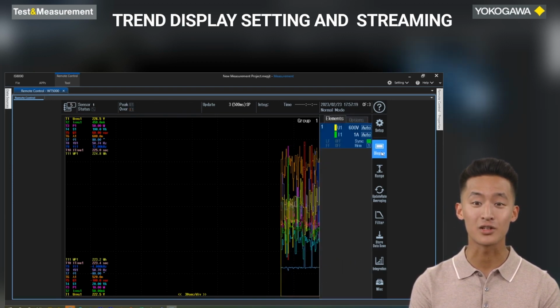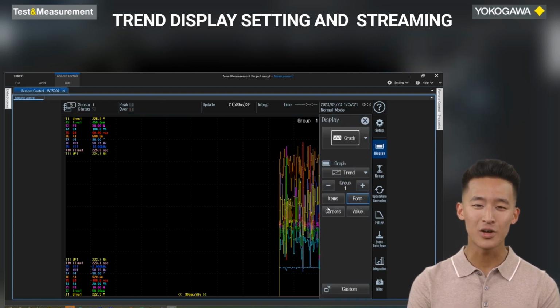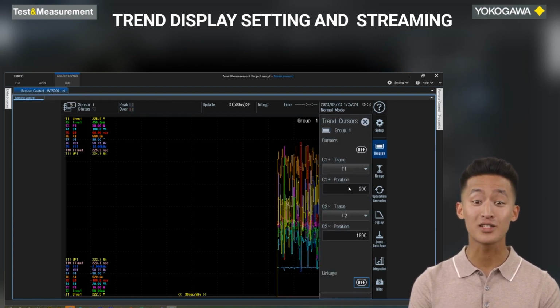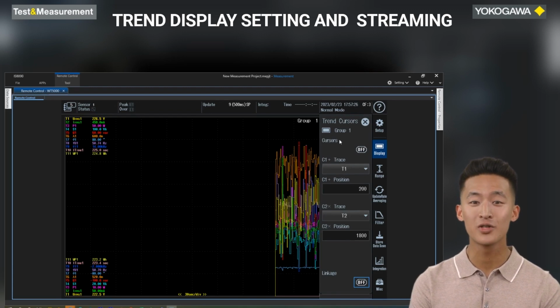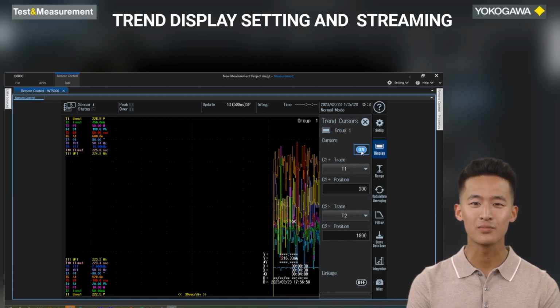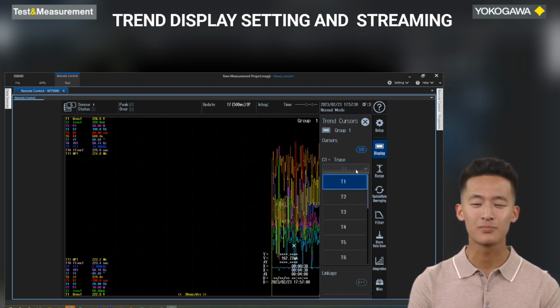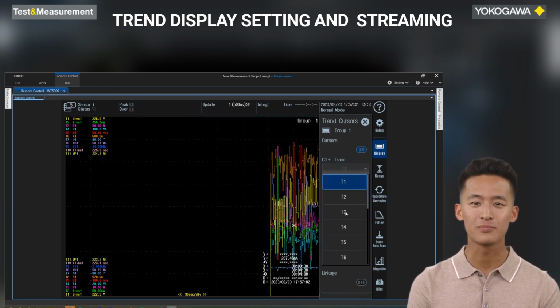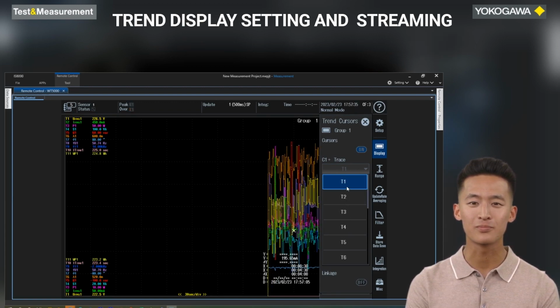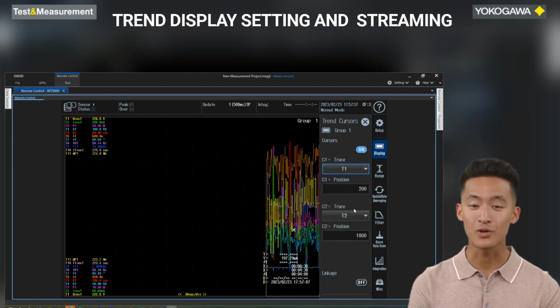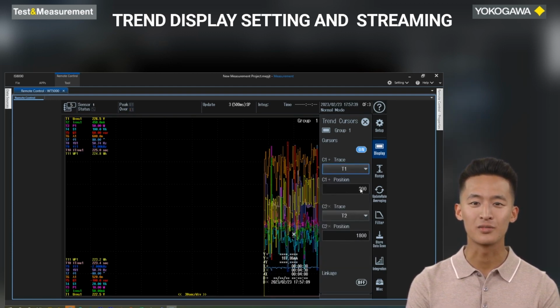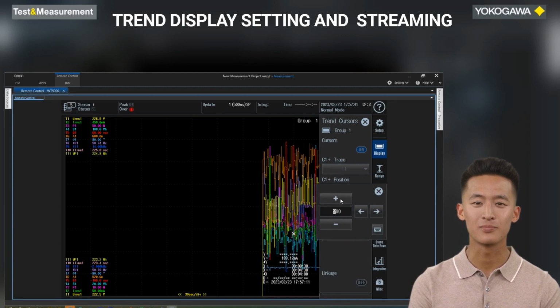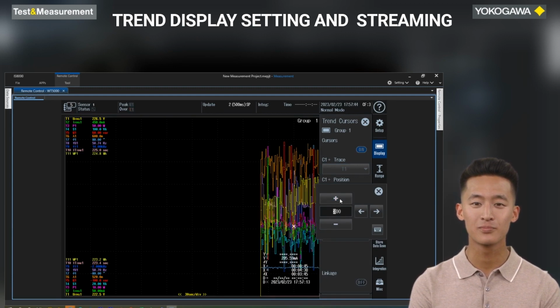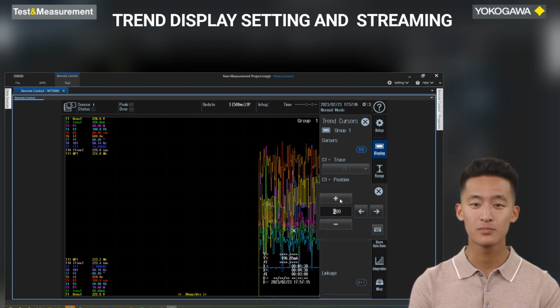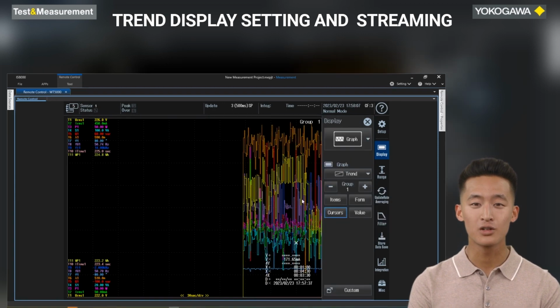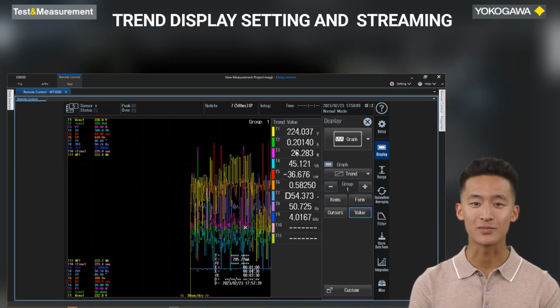Now let's understand the cursors in trend graphs. There are 2 cursors available with which we can see the trend parameters by switching on the cursors and selecting the required trace. With the help of cursor position, we can move the cursors. Let's close cursor window and click display again.